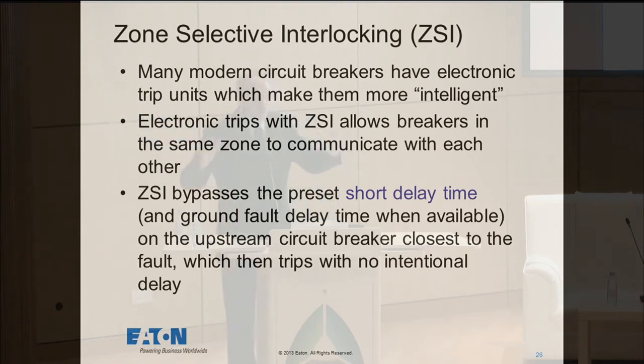So power breakers were made for big facilities to sit there and ride through these overcurrents, and they have delay settings. As I mentioned, they're tested for a delay setting of 1/2 second, which in an electrical fault situation is a very long time. That's made to sit there so that the one downstream from it opens. One of the things we have in a lot of these circuit breakers is what's called zone selective interlocking. These big circuit breakers all have electronics in them, and we're able to build intelligence into the electronics.